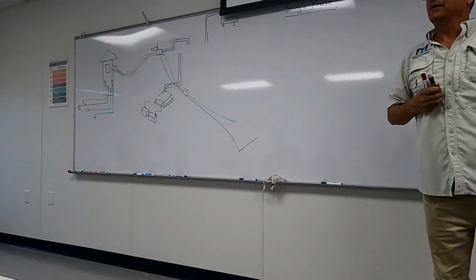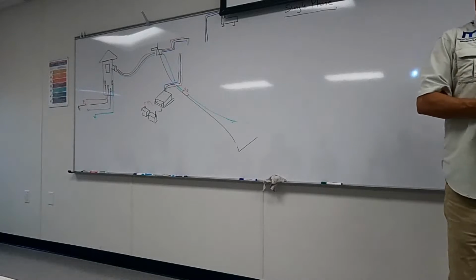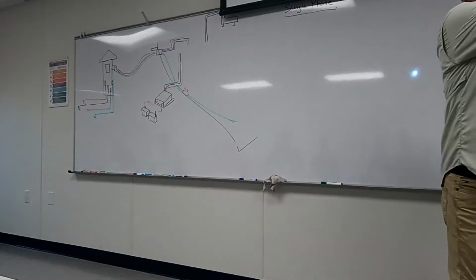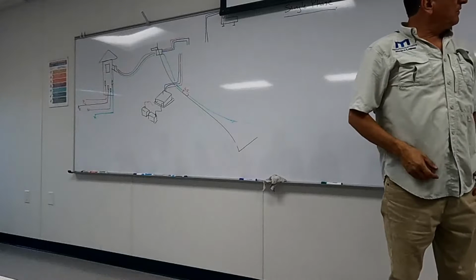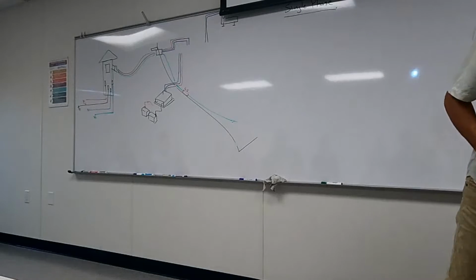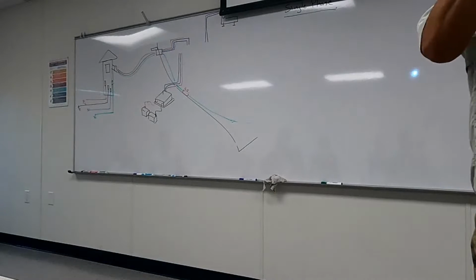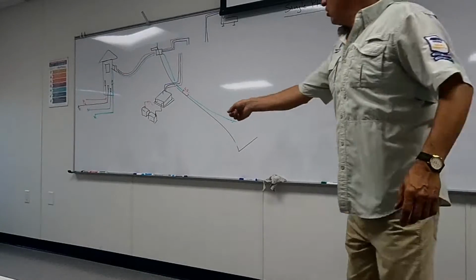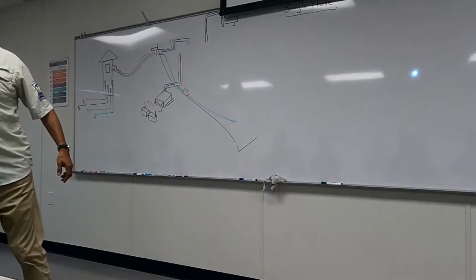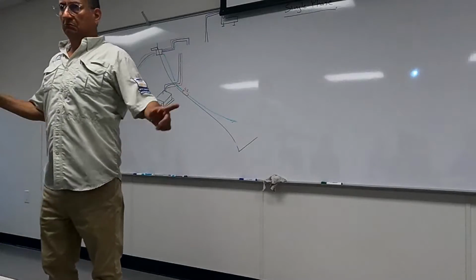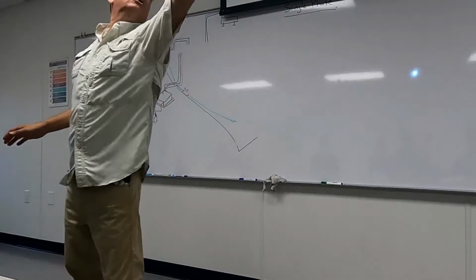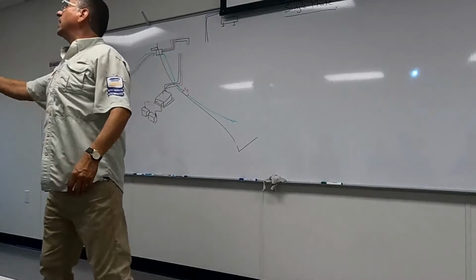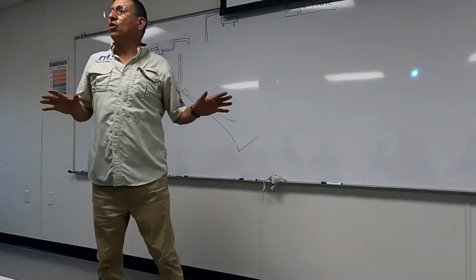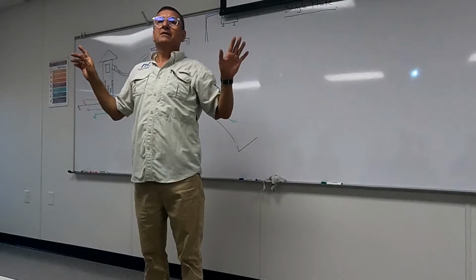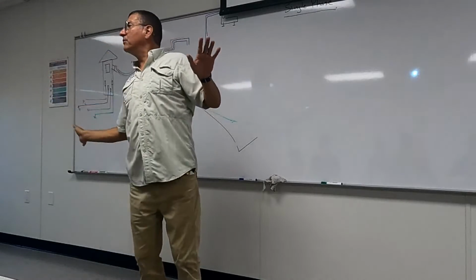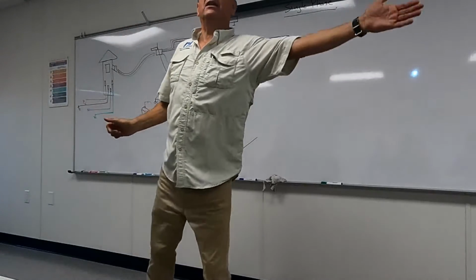You understand? Let's say I have a big room, I am going to divide it. All the outlets in this wall until the middle will be on the black phase, and all the outlets here until the middle on the red phase. One phase for those outlets and those lights, and the other phase for those outlets and lights. In other words, in this room I have 2 phases, but one phase is dedicated for those outlets and the other phase dedicated for the other outlets.